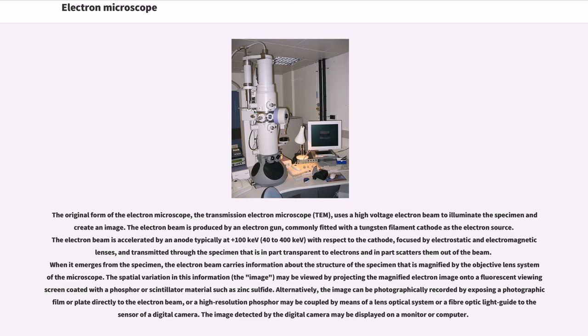with respect to the cathode. Focused by electrostatic and electromagnetic lenses, and transmitted through the specimen that is in part transparent to electrons and in part scatters them out of the beam. When it emerges from the specimen, the electron beam carries information about the structure of the specimen that is magnified by the objective lens system of the microscope. The spatial variation in this information, the image, may be viewed by projecting the magnified electron image onto a fluorescent viewing screen coated with a phosphor or scintillator material such as zinc sulfide.